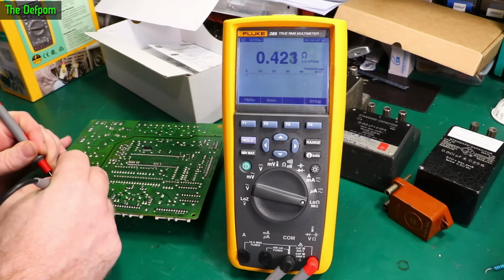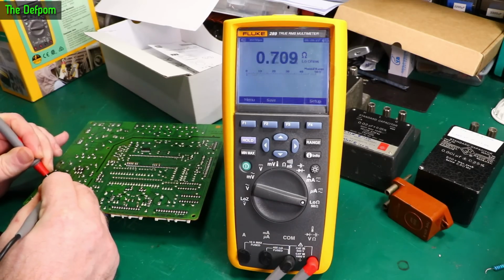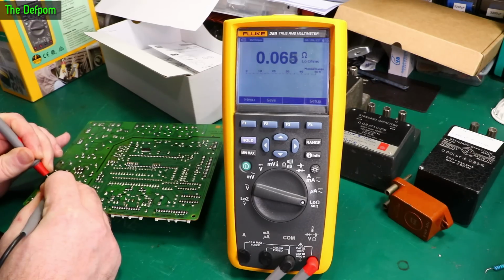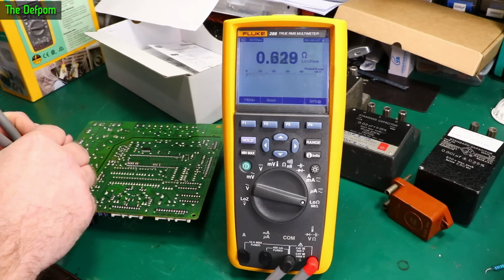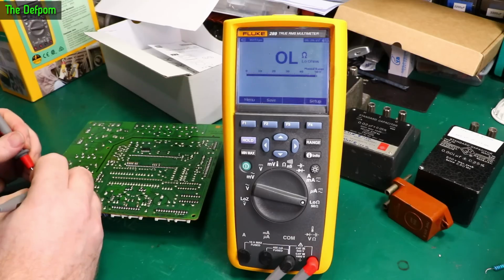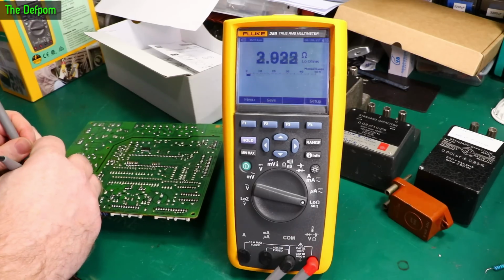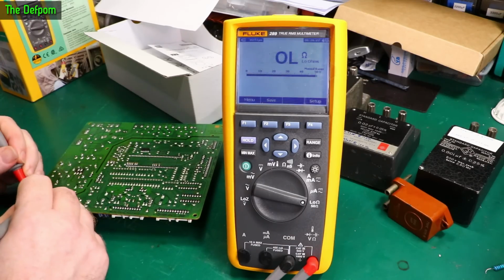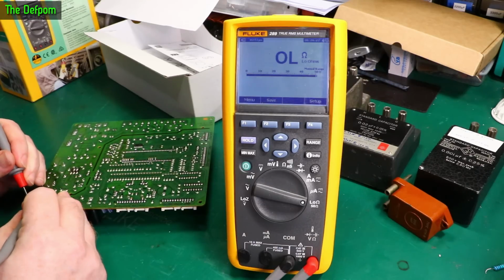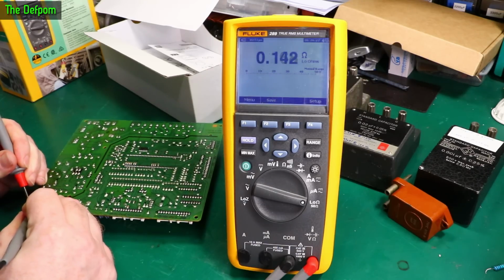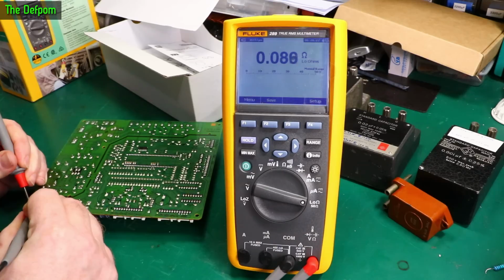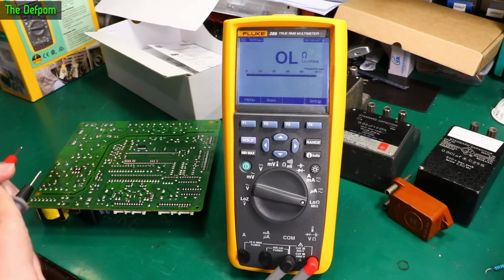0.44 ohms. Nice. If I put the leads together, it does have a bit of averaging in there, I think. Yeah, 0.065 or so. If I probe onto the actual pad, I do that. So that's like the meter zero. I suppose I could null that out. Yeah, it's alright. You can see low ohms there quite nicely. 2.8 ohms. The same over here. The others. There we go. Let's go short there, isn't it? 0.9 or so. Yeah, so that works alright.